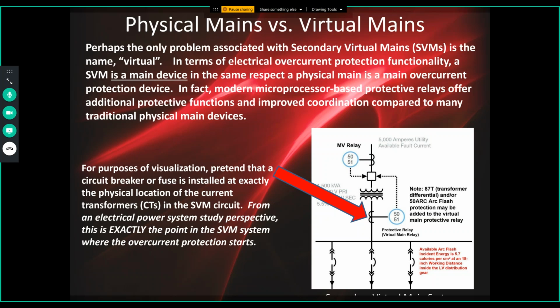In fact, it could be argued that modern microprocessor protective relays, such as pictured here, I'm only picturing 50 and 51 here, but as you can see, we can offer 87T and frequency protection and reverse power and under and over voltage. There's a variety of overcurrent protection functions that can be added in a secondary virtual main, which are typically not available in a physical secondary main.